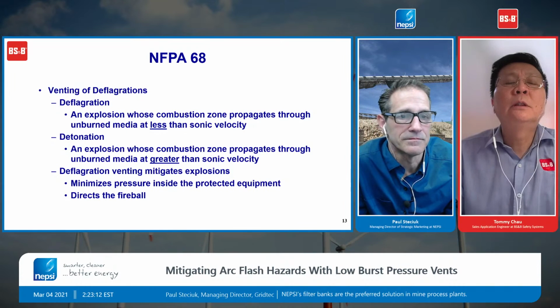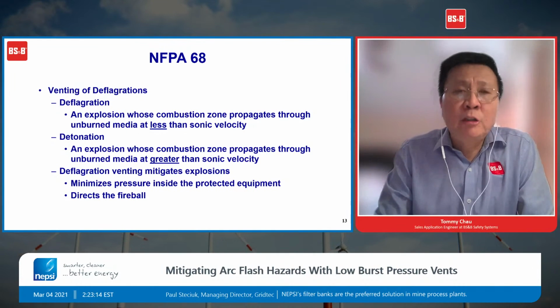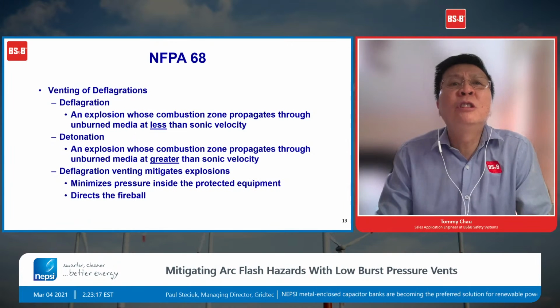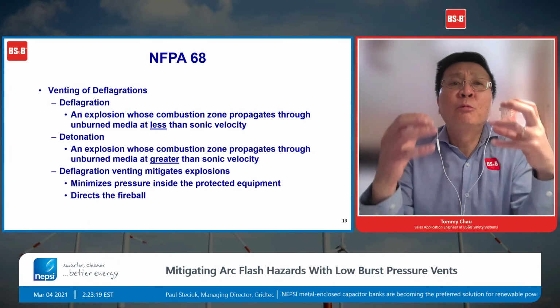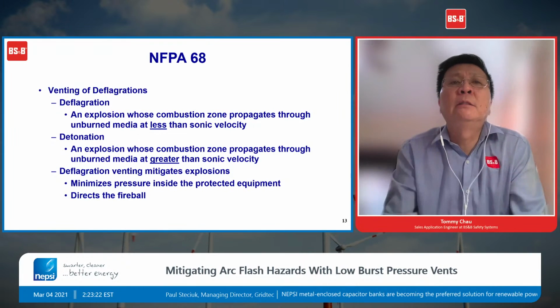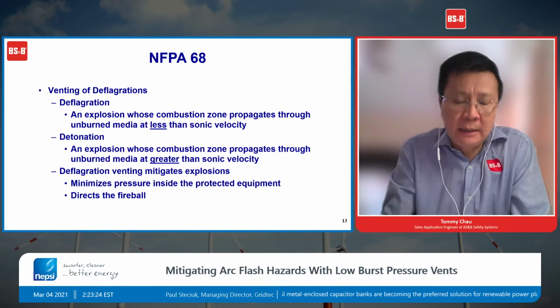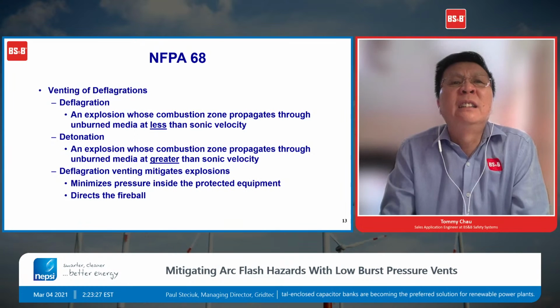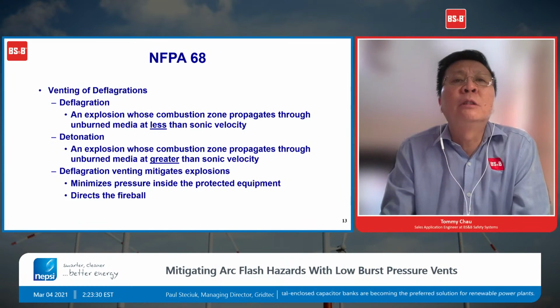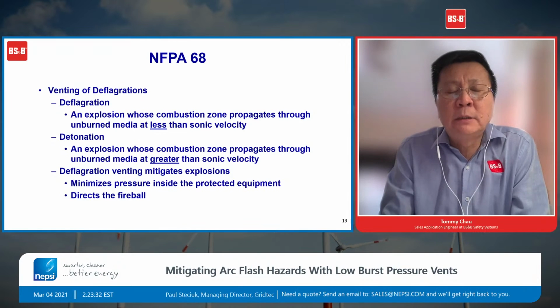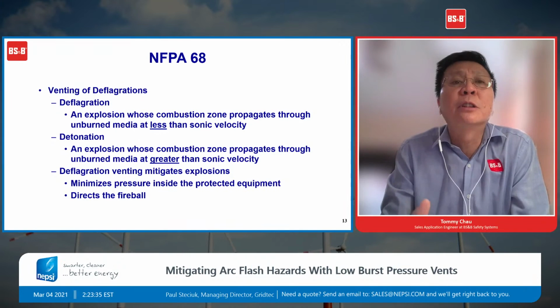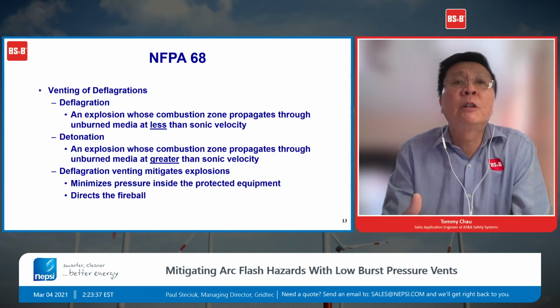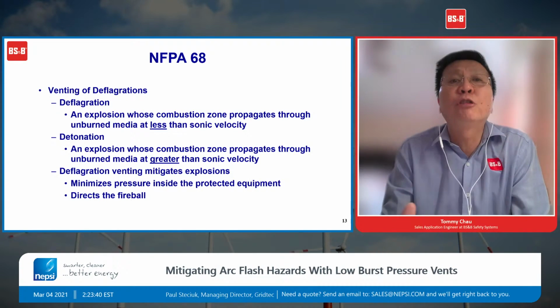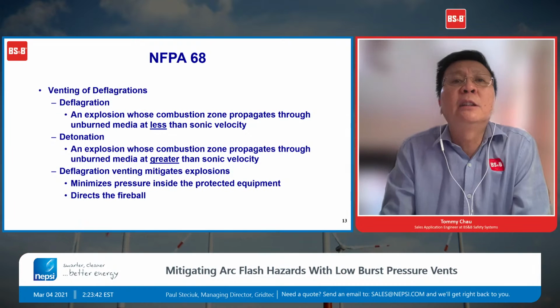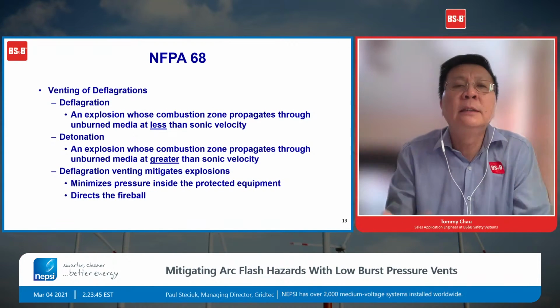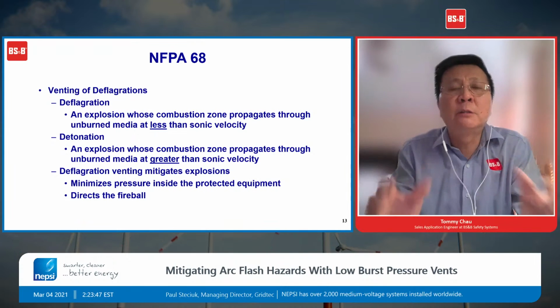Okay, so on venting and deflagration versus detonation, an explosion with the combustion zone can happen at less than the sonic velocity. And we mentioned earlier, detonation is something that we typically stay away from because it happens so fast. So deflagration venting is, again, to minimize the pressure inside your protected equipment, and then basically you want to direct and take all the pressure and the fireball to a safe and isolated area.